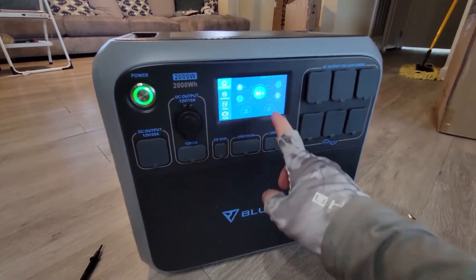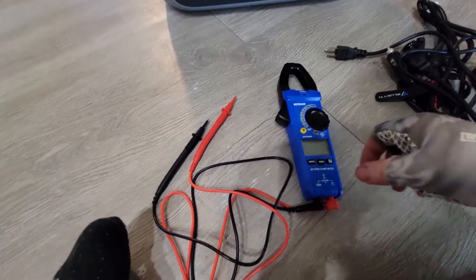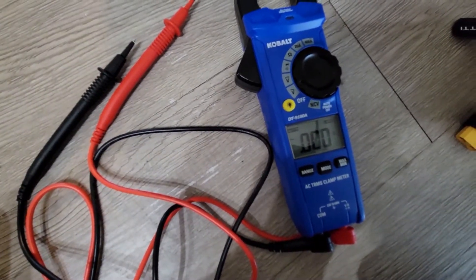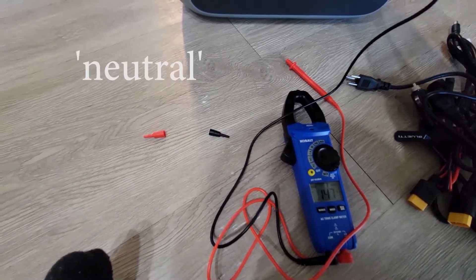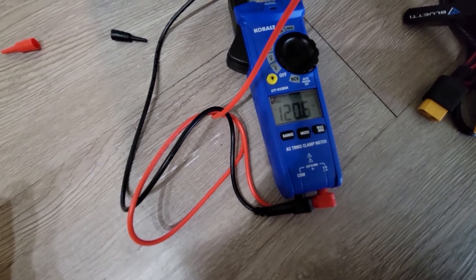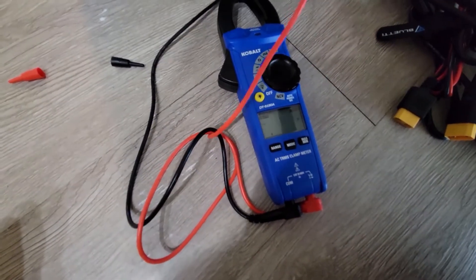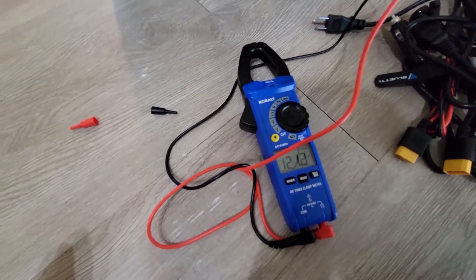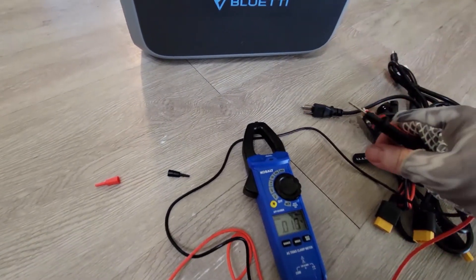I'm going to test out these plugs. This is a Kobalt clamp-style multimeter. I'm going to throw it on alternating current volts, where your little sine wave is. I'll take off my CAT 3-4 adapters and connect my ground first. Reading a clean 120-121 volts. I'll try a couple more plugs to make sure they're all working. If you don't feel comfortable using a multimeter, please don't use one. Those all look good.